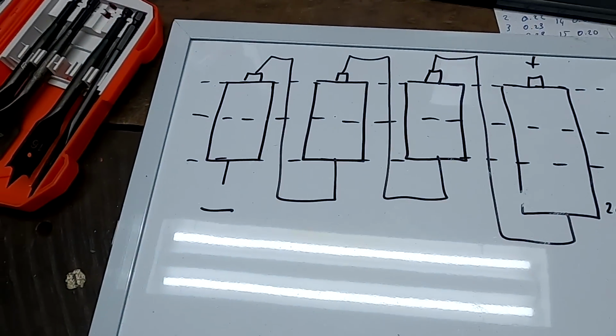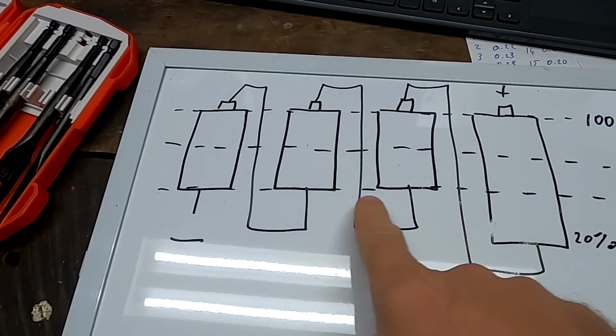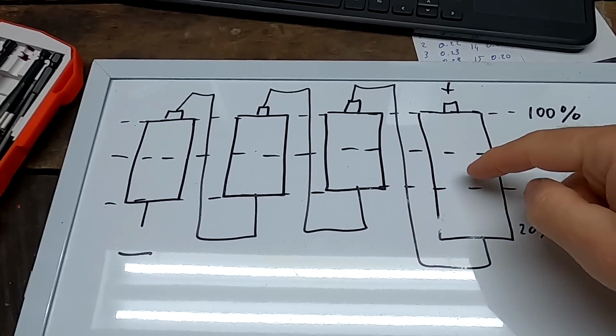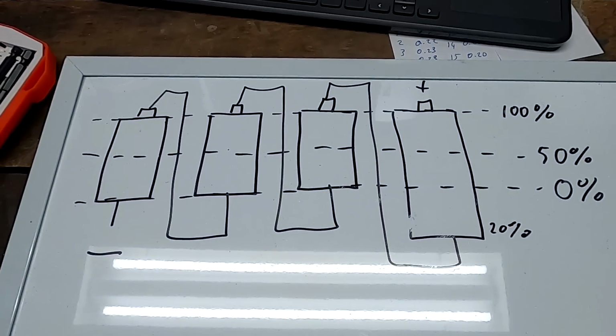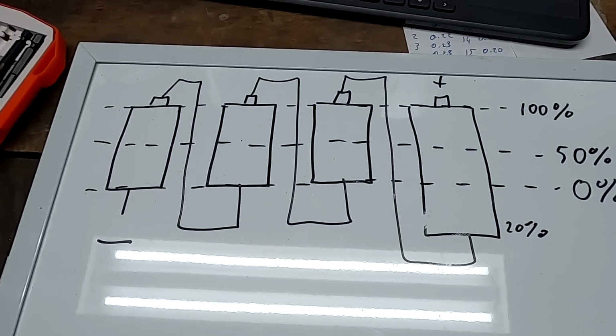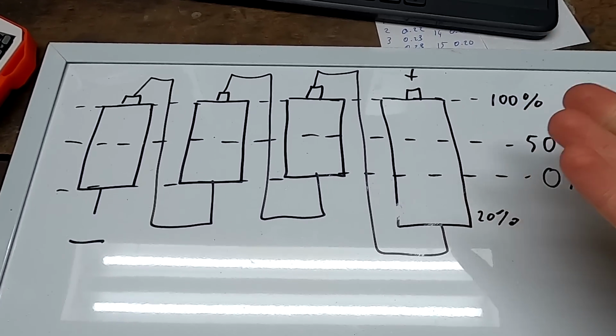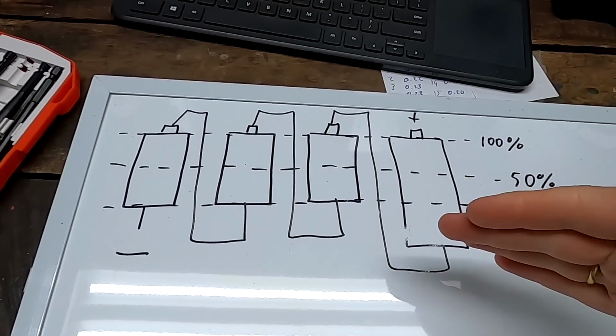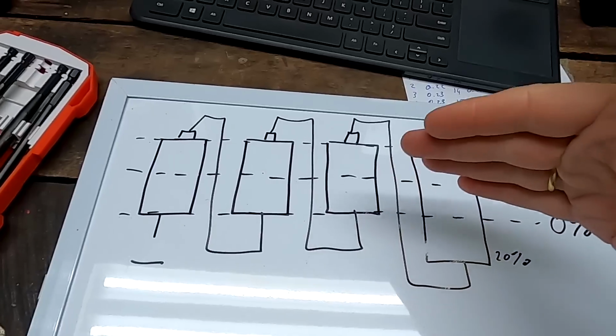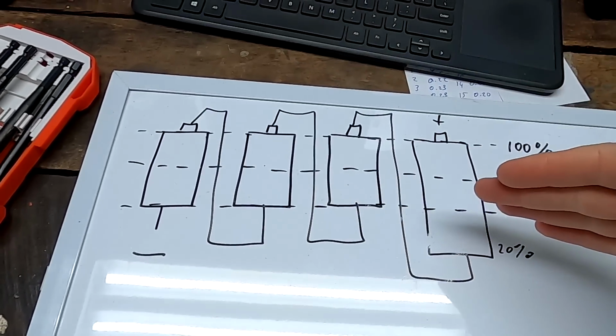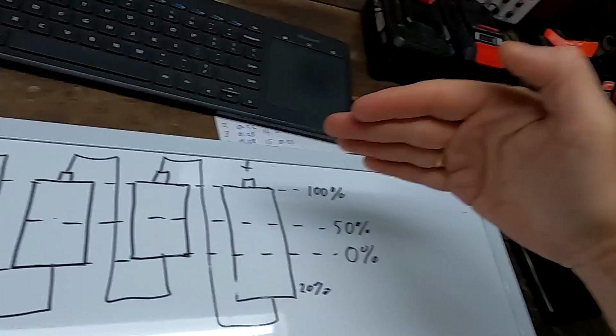So here again, we are exactly at this position now, 0% state of charge of the whole battery, but these 304 ampere hour batteries still have a bit of capacity left, like 24 ampere hours maximum. Now we're going to fully charge the battery again, adding another 280 ampere hours to all the cells, and they should all meet again at 100% state of charge, more or less. The top balancing is still intact, and we'll check this in the next couple of days.